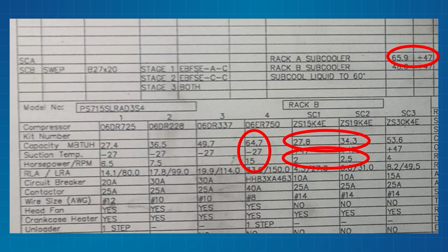This becomes even more pronounced as we go down to subcooled temperature. Every BTU I'm removing from that liquid is a BTU my compressor doesn't have to work as hard for. So if I can do that at 47 degrees instead of minus 27, it's a giant energy saver. About 10 horsepower, ballpark, just on this one subcooler, at 60 degrees.